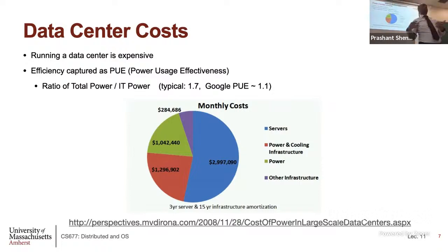Because that's going to increase your electricity bill, there's been a lot of research on how to reduce the PUE of the data center, or just how to make the data center more energy efficient. The ideal value is now coming down, and the most efficient data centers today have PUE values of 1.1 or lower, maybe 1.07, 1.1. What that means is they made the cooling extremely efficient.